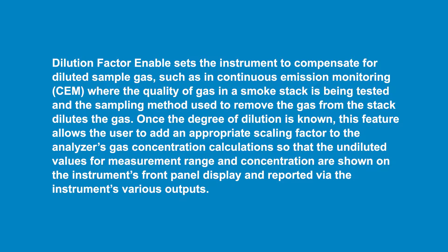Dilution factor enable sets the instrument to compensate for diluted sample gas, such as in continuous emission monitoring, where the quality of gas in a smokestack is being tested and the sampling method used to remove the gas from the stack dilutes the gas. Once the degree of dilution is known, this feature allows the user to add an appropriate scaling factor to the analyzer's gas concentration calculations so that the undiluted values for measurement range and concentration are shown on the instrument's front panel display and reported via the instrument's various outputs.